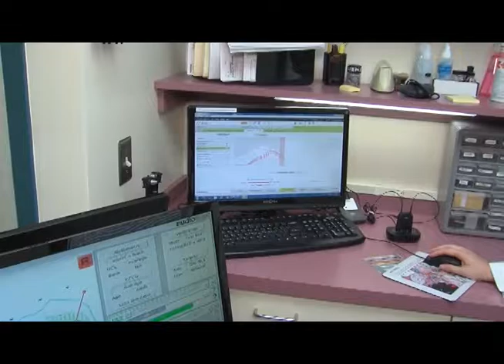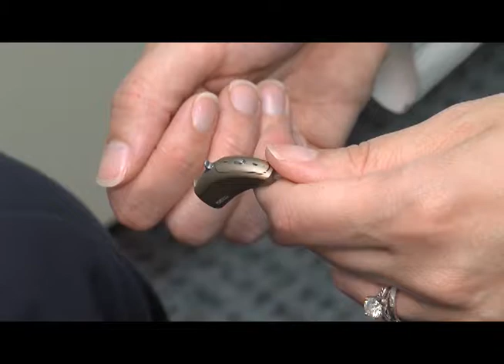In addition to measuring the frequency range to try to get it appropriate and hopefully not amplify things he doesn't need to hear, we also have other settings in the hearing aid. So for example, we can set the hearing aids so that really loud sounds will not be uncomfortable and soft sounds will still be audible to him. The hearing aids now are automatic, they are digital, and so once we've got them set to the point that they pretty much meet the specifications of the hearing loss for the individual with whom we're working, then they don't have to do a great deal with the hearing aids. Some of them you can adjust if you need to, but the goal is to set the hearing aids so that the patient can put them in and pretty much just wear them with the hearing aid doing its own adjusting depending on the environment that you're in. And so that's the primary purpose of doing an acoustic fit.